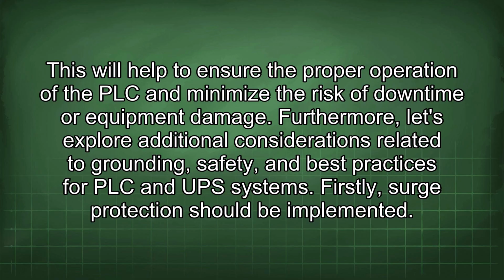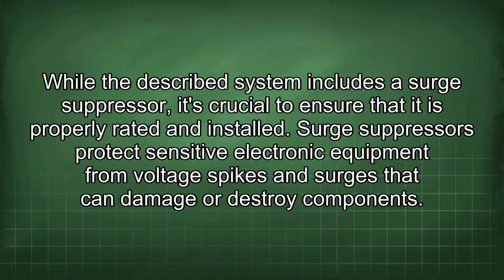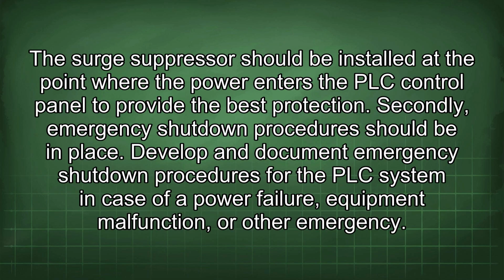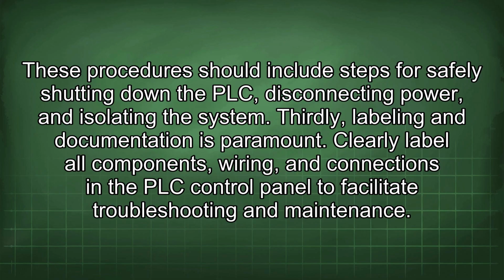Firstly, surge protection should be implemented. While the described system includes a surge suppressor, it's crucial to ensure that it is properly rated and installed. Surge suppressors protect sensitive electronic equipment from voltage spikes and surges that can damage or destroy components. The surge suppressor should be installed at the point where the power enters the PLC control panel to provide the best protection. Secondly, emergency shutdown procedures should be in place. Develop and document emergency shutdown procedures for the PLC system in case of a power failure, equipment malfunction, or other emergency. These procedures should include steps for safely shutting down the PLC, disconnecting power, and isolating the system.